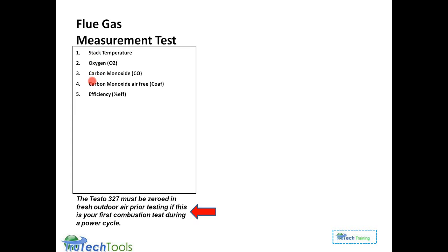Percent efficiency is the next parameter. That's the combustion efficiency. The excess air, which is another calculated parameter. And by the way, you can switch any of these off. If all you wanted to measure was oxygen and CO, for example, those would be the only two things on your display. You could switch everything off, and you haven't permanently deleted them. You just switched them off, so they're not available on the display, not available on the printer. You can go back in at any time and reactivate those and put them in any order you want.